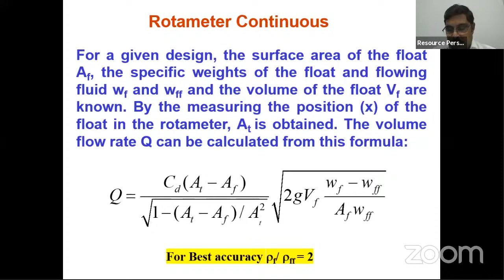So in this expression, K is constant, AF is constant. The only variable is AT, which will vary with respect to float position. So by observing the float position, measuring the float position, the flow rate can be measured. So in the rotameter, you can see there will be a calibrated scale.